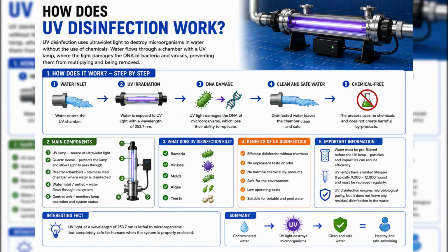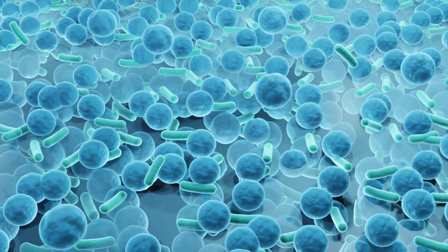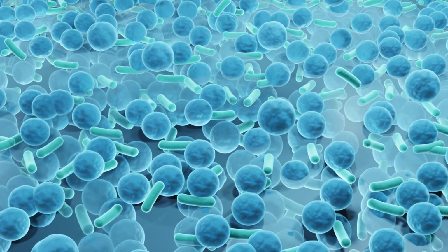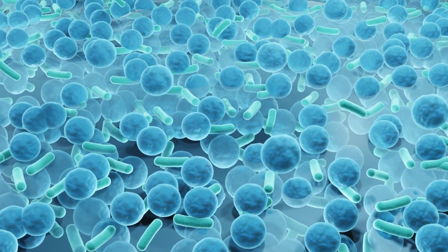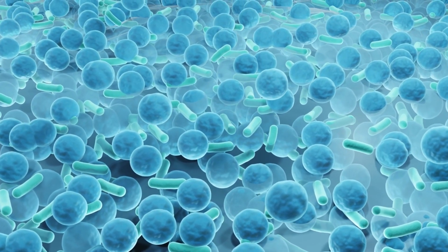Pool water is pumped through a chamber containing a source of ultraviolet radiation. The UV radiation can damage the genetic material of microorganisms and prevent them from reproducing effectively. But UV has an important limitation. It only treats the water that is passing through the UV chamber at that moment. Once the water returns to the swimming pool, the UV radiation does not remain in the water as a residual disinfectant. For this reason, UV treatment is commonly used as a supplement to another disinfection system, rather than as a simple replacement for all chemical treatment.